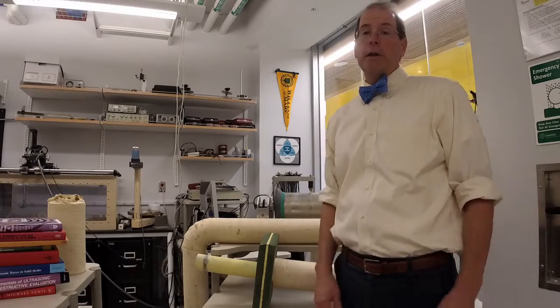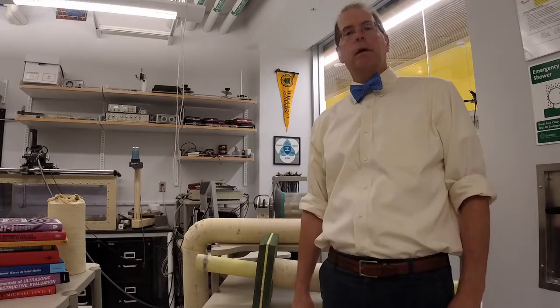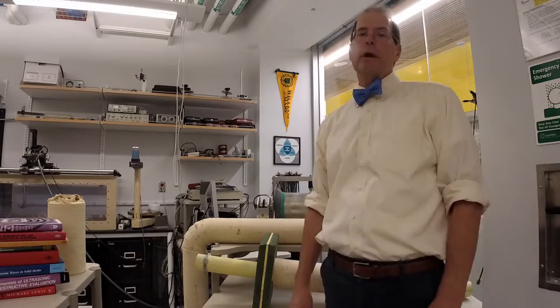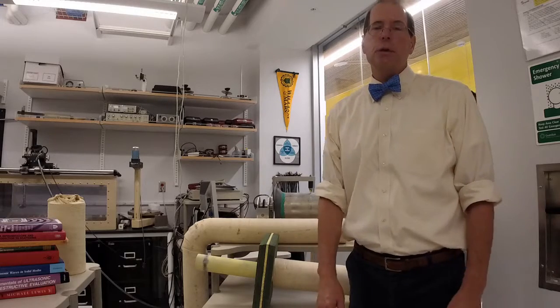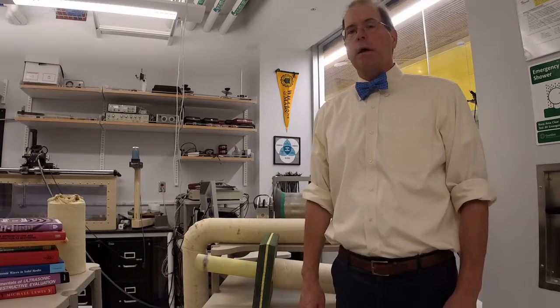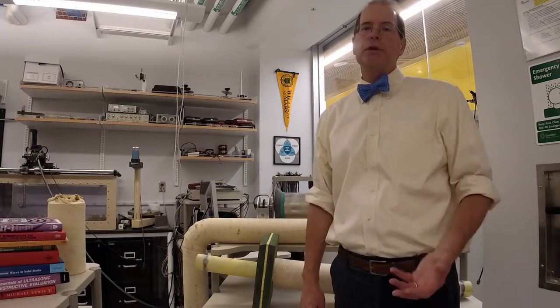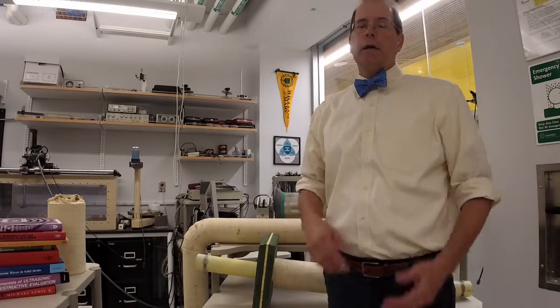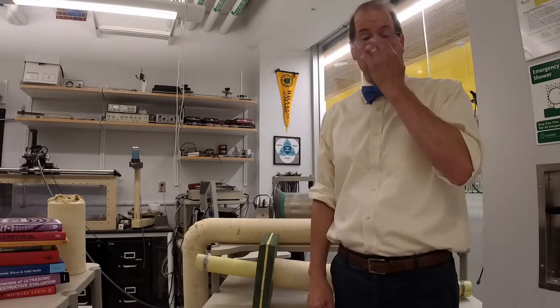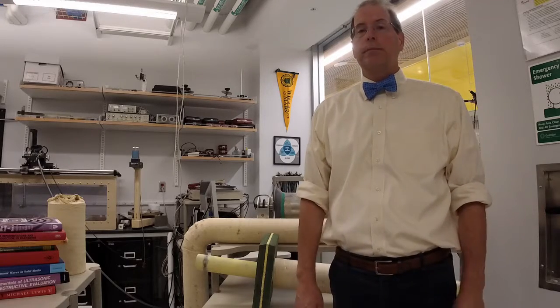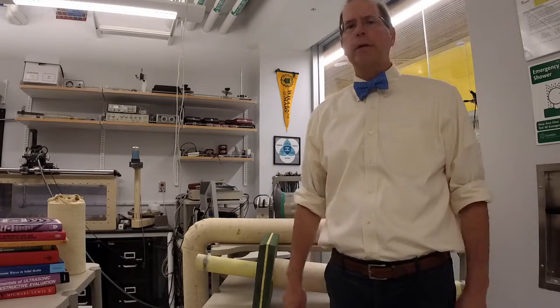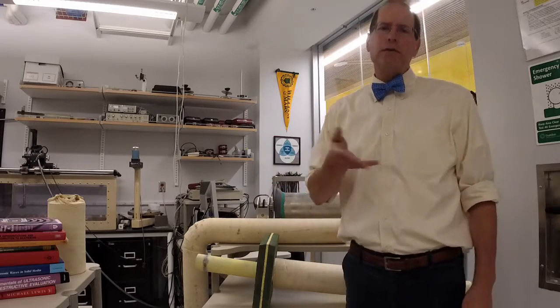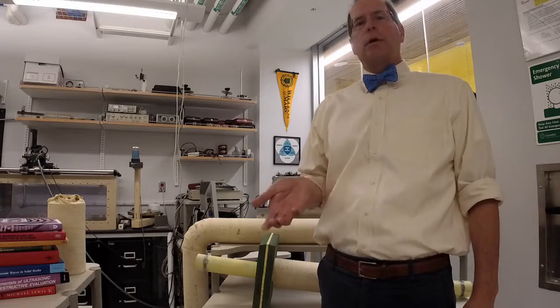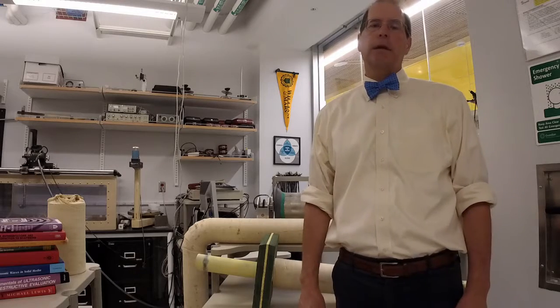We also developed the helical ultrasonic tomography for inspecting gun barrels. The issue with gun barrels, Army howitzers, is not corrosion but erosion on the inside, which affects accuracy. So we initially began developing this for the Army to put belts of transducers around the outside, and then at one point they said, no, we're going to put heat shields on the outside, so we really need a version that can go inside the gun barrel and inspect it that way.